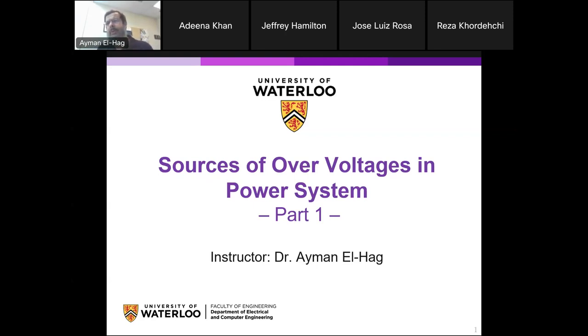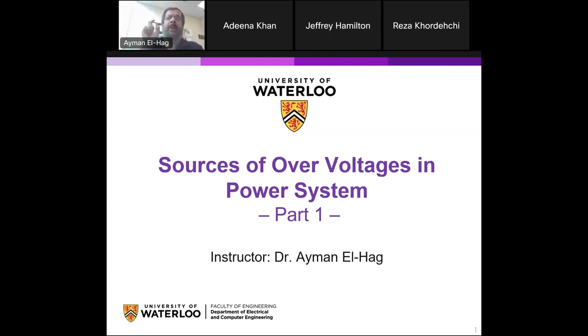I would like to look at these two lectures as the connection between high voltage engineering and the power system, because those overvoltages are due to some operations in the power system. Even if you are a high voltage engineer who works in insulation, it's very important to understand the link between the two. What is the impact, for example, if you have a switching happening in the system, or a lightning strike, and how this will contribute to the generation of high voltages that can impact your equipment.